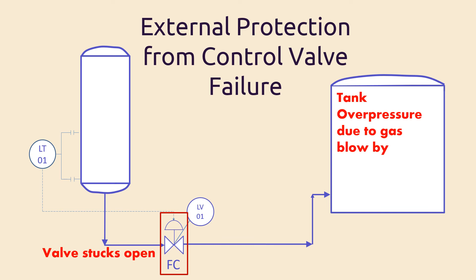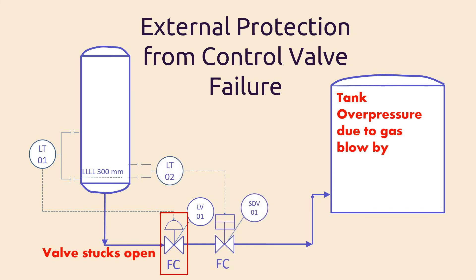In this case, we shall need to stop the fluid flow once the liquid level in the vessel reaches the low-low liquid level, let's say 300 millimeters. This can be done by installing a level transmitter on the vessel that sends a signal to an on-off shutdown valve to close it once the liquid level is 300 millimeters. So the scheme shall look this way. But in many cases, depending on shutdown protection may not be enough.